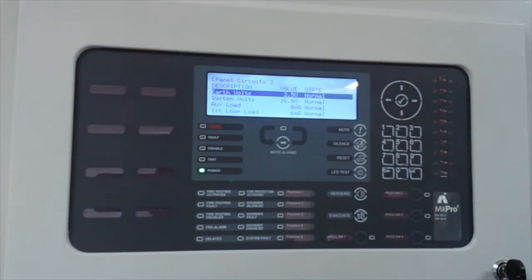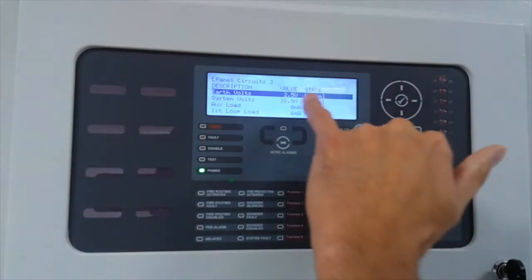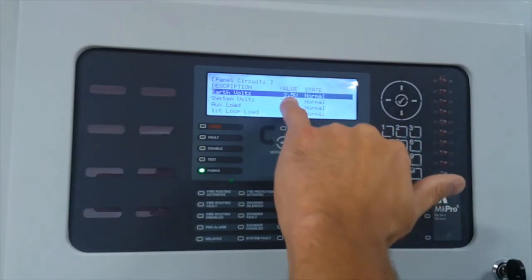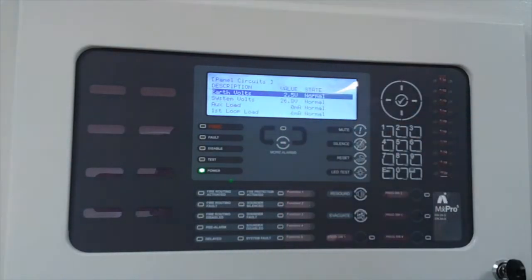If that earth voltage goes greater than three and a half or say four volts, that's a positive conductor to ground. If this voltage drops less than one and a half volts, then it's a negative conductor to ground.